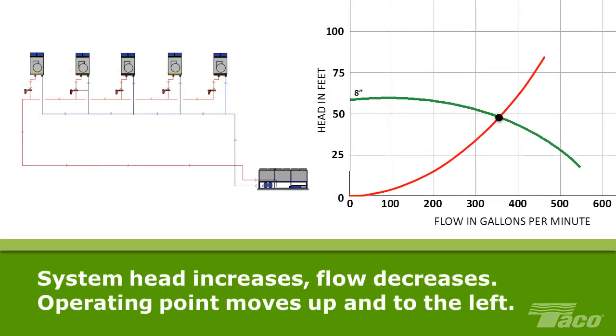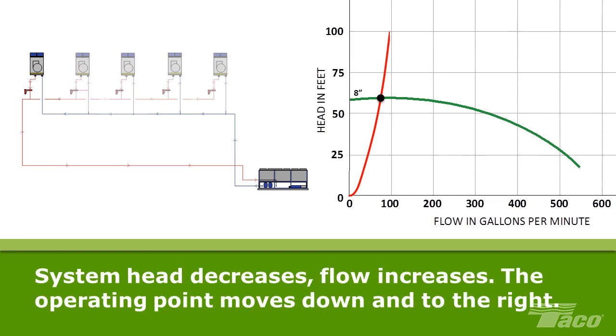As we can see by the movement of the system curve, as head in the system increases, flow decreases. As a result, the point where the curves intersect, which represents the system operating point at a particular moment, moves up and to the left on the pump curve. When the opposite occurs, as system head decreases and flow increases, the point at which this system curve intersects with the pump curve changes again, in this instance moving down and to the right along the pump curve.